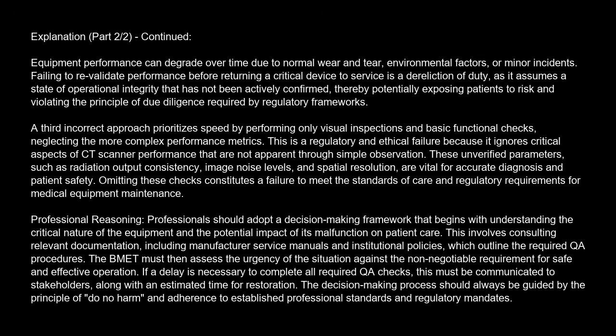A third incorrect approach prioritizes speed by performing only visual inspections and basic functional checks, neglecting the more complex performance metrics. This is a regulatory and ethical failure because it ignores critical aspects of CT scanner performance that are not apparent through simple observation. These unverified parameters, such as radiation output consistency, image noise levels, and spatial resolution, are vital for accurate diagnosis and patient safety. Omitting these checks constitutes a failure to meet the standards of care and regulatory requirements for medical equipment maintenance.